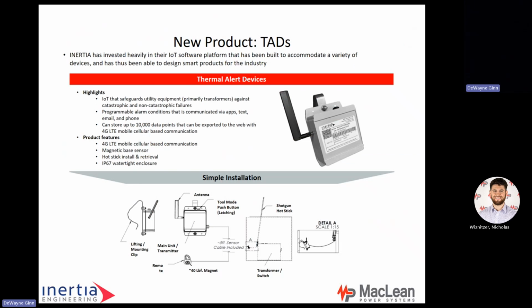TADs, thermal alert devices. We talked about those earlier. So what a TAD is: I put a sensor on the side of a transformer, primarily in-ground transformers or in vaults. The sensor is put on with a hook stick and it's magnetic, and it goes right to the side of the case. So that gives us information on the temperature rise of the transformer. It goes back to the monitor and gives us data back to a cloud-based collector.